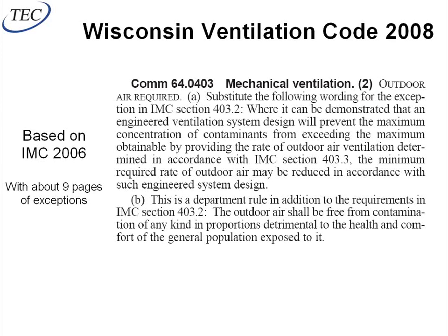For those of you doing work in Wisconsin, I know it is a widely held belief in the state of Wisconsin that you can't use CO2, but that is not the case. It's not true. You can do CO2 systems. You just have to be a little bit more cognizant about talking to the permit and inspector guys, because they might not quite understand what it is. So I point this out here. This is the section you want to show them.